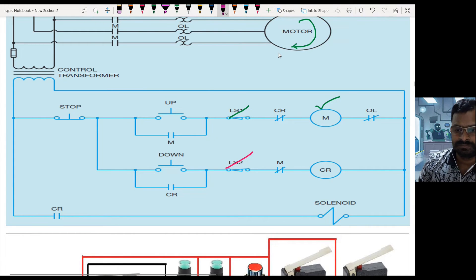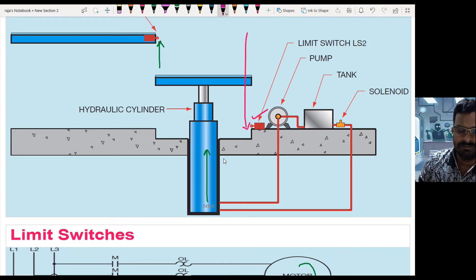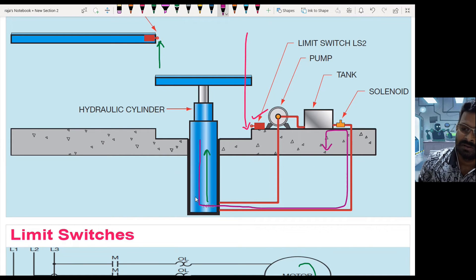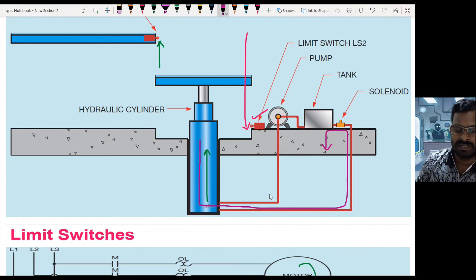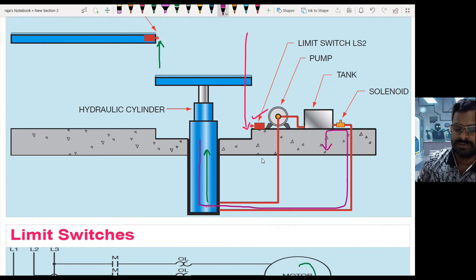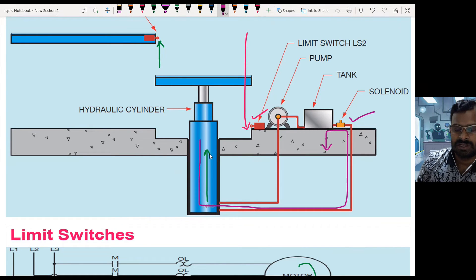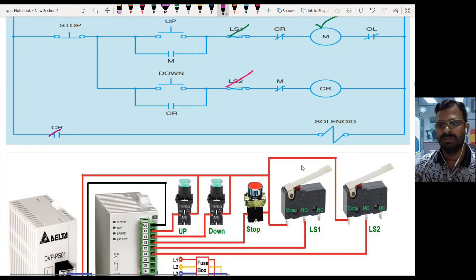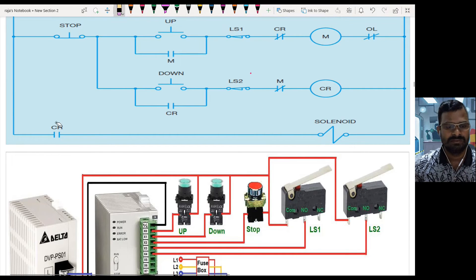When the control relay is energized, its contact closes. As the cylinder comes back, the fluid inside the cylinder flows through this path to the tank. The return path is controlled through the solenoid valve, while the forward motion is directly connected to the cylinder. When the pump is on, fluid enters the cylinder for forward motion. When coming back, we turn off the motor and enable the solenoid, so due to the cylinder piston's weight it comes down and liquid flows to the return tank.